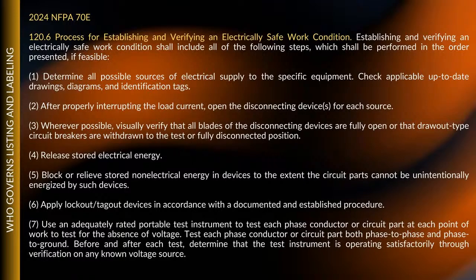They tell you, after properly interrupting the load, open the disconnecting devices for each source. Wherever possible with a disconnecting device, they want you to visually verify that all blades have been fully opened, or that draw-out circuit breakers are withdrawn to the test or fully disconnected position.